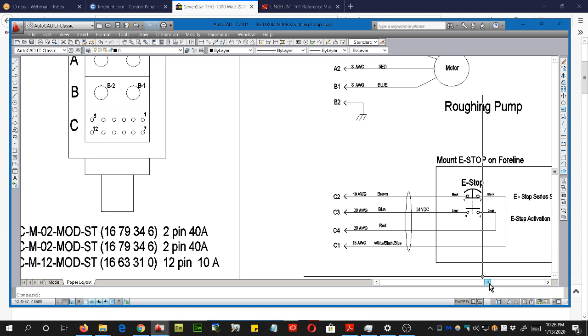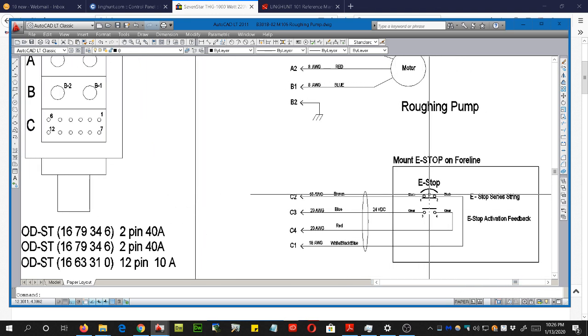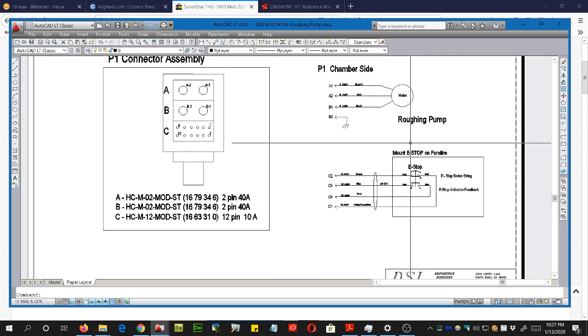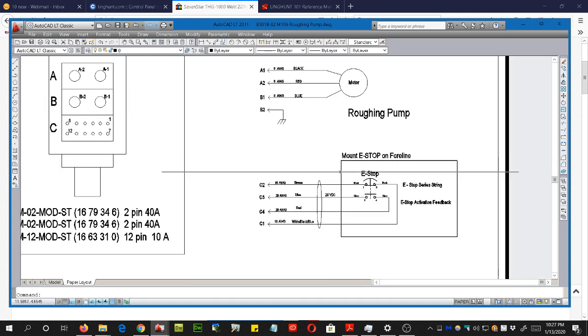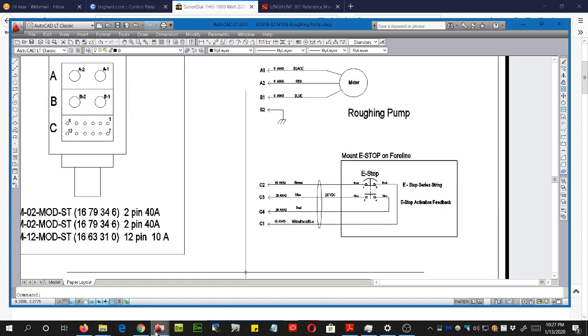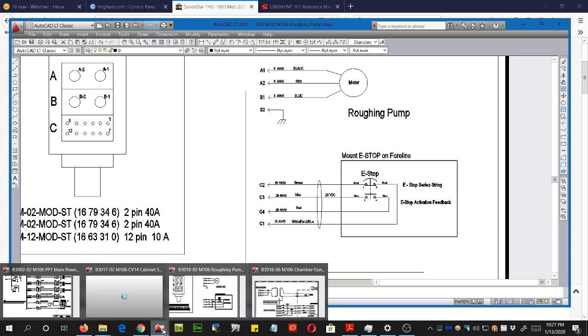The other plugs are, I'll run an e-stop through all the different e-stops on the machine, so it's all in series, but I'll also have another little contact block here, so if somebody pushes it, this sends a little signal back to the computer, and the computer knows that, hey, somebody pushed e-stop 1 on the foreline here, so that's where it was mounted. And they'll have that information, so they don't have to try to go, which one was it that got pushed? And anytime you have a machine and you got 14 e-stops on there, or even 2, they all got to do the exact same thing. Period. That's a very important one. I've seen that broken all the freaking time. But anyway, I digress. Close this, go to the other one.